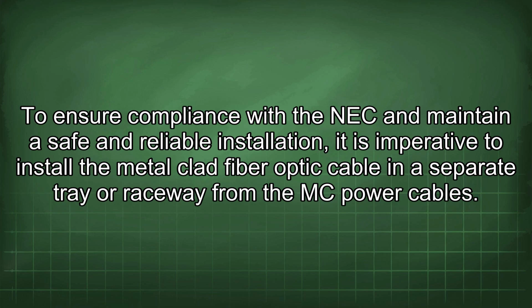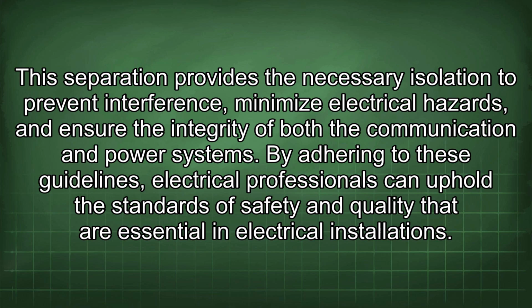To ensure compliance with the NEC and maintain a safe and reliable installation, it is imperative to install the metal-clad fiber optic cable in a separate tray or raceway from the MC power cables. This separation provides the necessary isolation to prevent interference, minimize electrical hazards, and ensure the integrity of both the communication and power systems. By adhering to these guidelines, electrical professionals can uphold the standards of safety and quality that are essential in electrical installations.